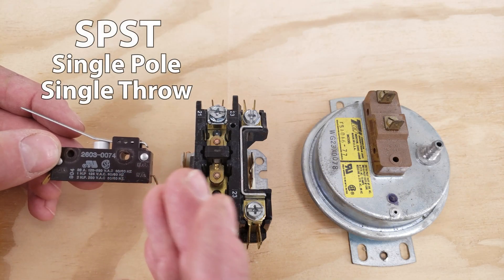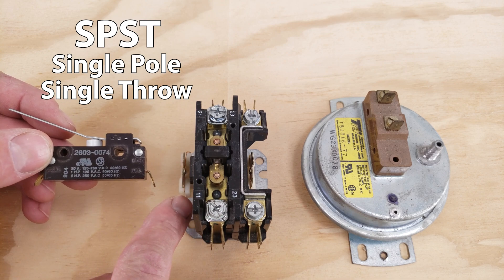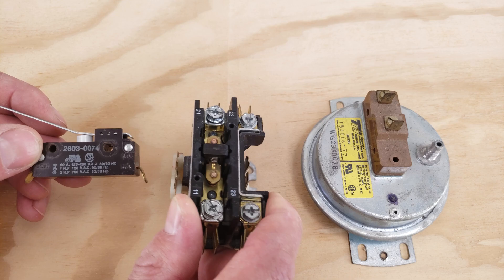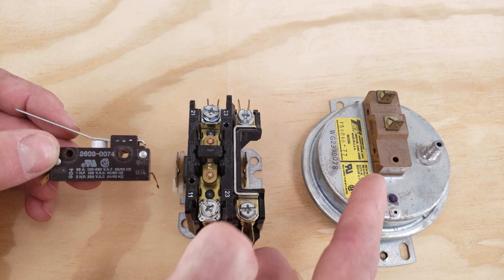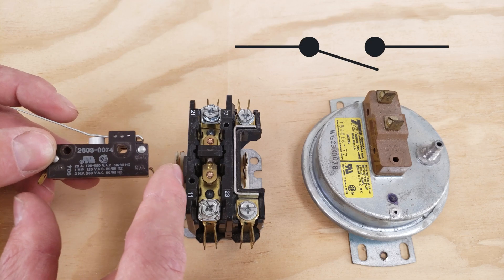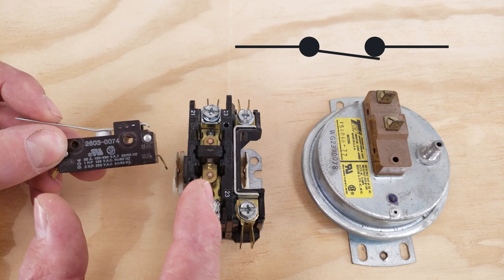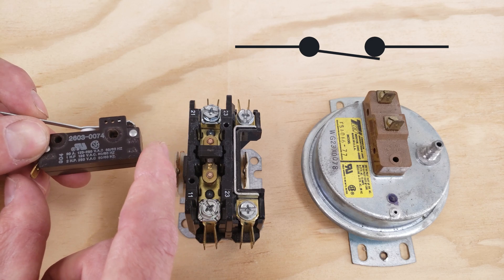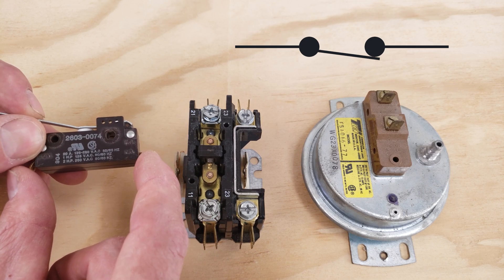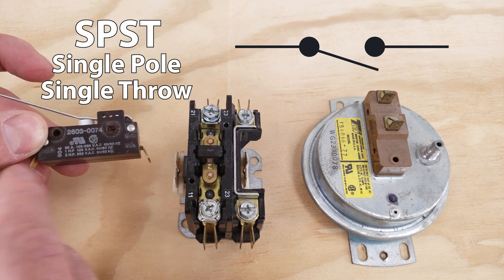First up is a single pole single throw switch. Remember, even though this is a mechanical switch, this is an electrical relay switch, and this is a pressure switch — that part doesn't matter as much as just the contacts. Even though this is in the open position now and when you push the button in it's closed, anytime you have two contacts that's going to be a single pole single throw because there's only one action that happens.